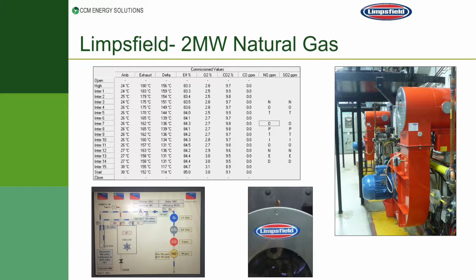Just a couple of applications with the Limpsfield burners. So this is a project at Alice Springs. These are two megawatt John Thompson water tube boilers. We installed dual fuel burners, natural gas and diesel. And this is the combustion results as taken from the analyzer. Importantly, you can see here the oxygen readings, 2.5 up to 3%. And that was 6-1 at that point here. The last 2 points, the customer wanted us to give them 9-1 on that site. So hence we had to go over that 3% to 3.1.